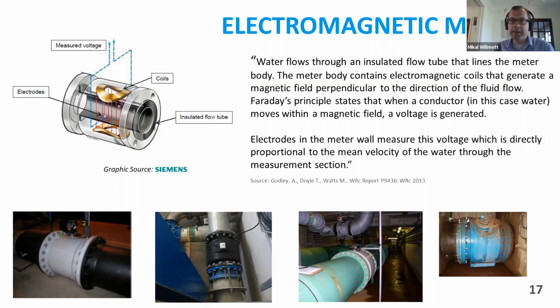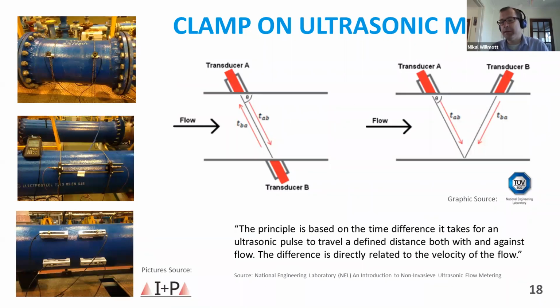Can we just move on, Andy, please? And again, a really basic description of clamp-on ultrasonic meters. On the left-hand side, you'll see some pictures of clamp-on ultrasonic meters. Essentially, you have two transducers. They clamp onto the side of the pipe, and the transducer sends and receives ultrasonic pulses. Because we know the diameter of the pipe and the distance between the transducers, the meter can calculate the flow rate based on how quickly pulses are getting from one transducer to another. You can do this with a pair of transducers or several pairs of transducers and then average the flow rate. There's a few different setups.